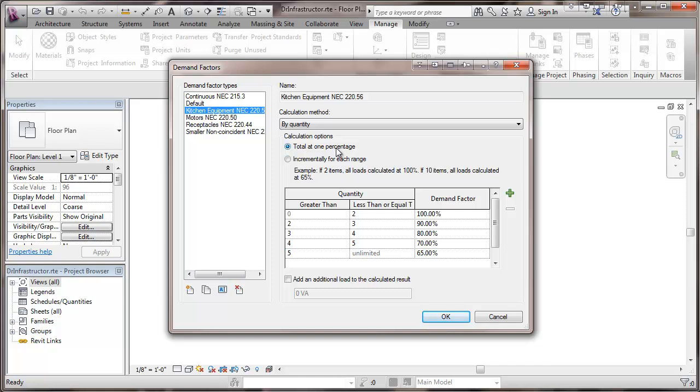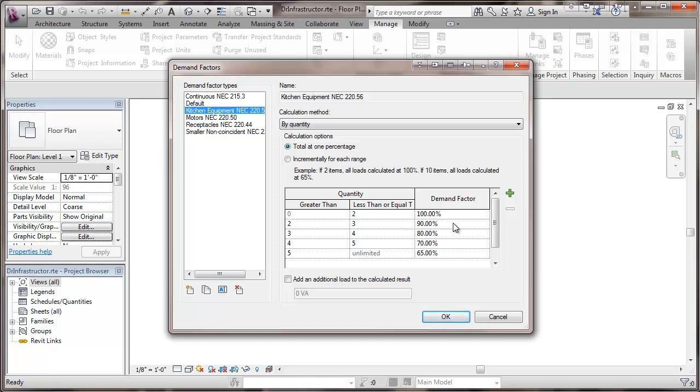All of these demand factors are in accordance with NEC chapters which are shown, so in terms of what's included under this type of demand you need to refer to the code. Here we have total at one percentage and for kitchen equipment that's thermostatically controlled if we have greater than two pieces of equipment it's a 90 percent demand factor for the whole thing and so on increasing numbers of equipment.